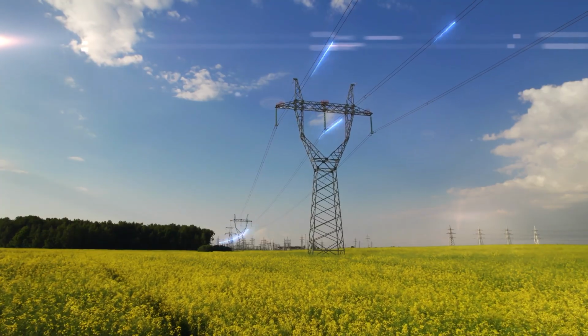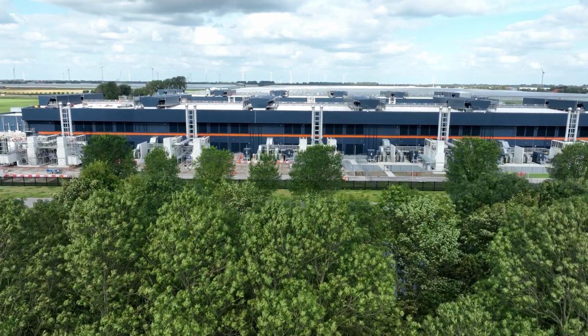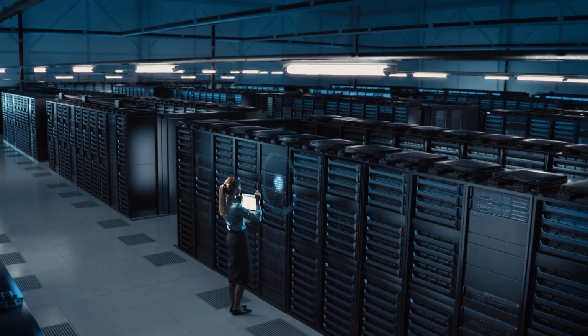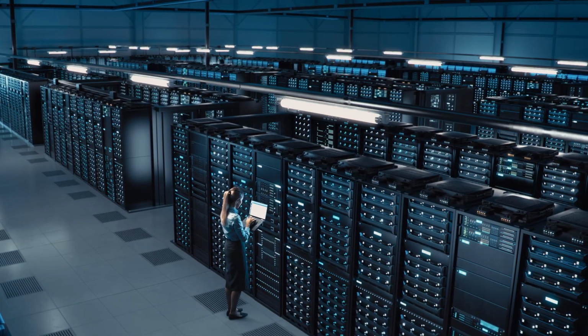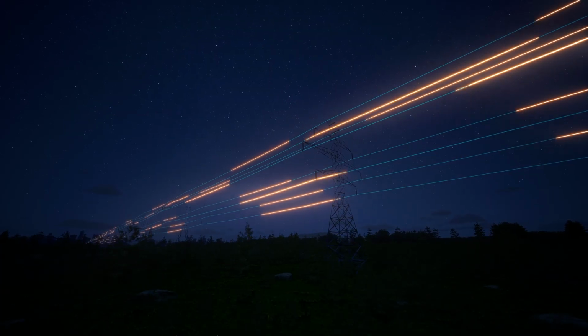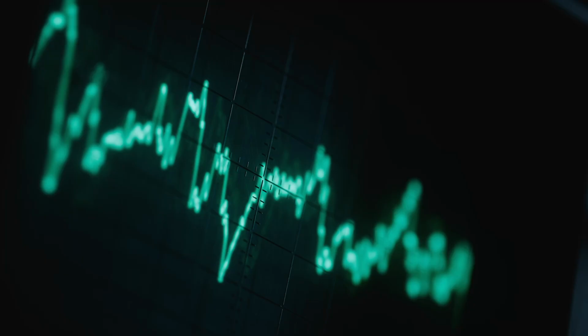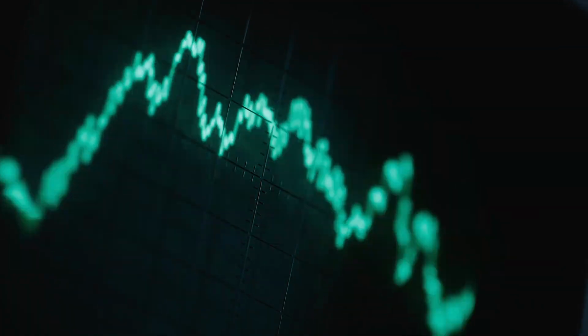The TerraFlow Energy solution is a win for the grid by being a controllable and responsive load. It's a win for AI data centers because it handles all the problems they're having with power volatility and harmonic distortion—all of it absorbed by the battery, with no degradation in cycles, so the batteries last a long time. Instead of giving you 1 to 2 hours with a lithium-ion battery and 10 minutes of UPS, we're putting in 10 hours of storage. It actually solves all the problems in one solution.